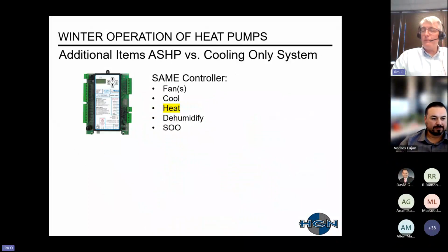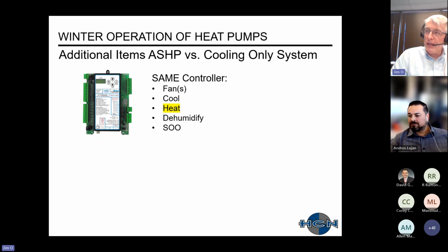And then just the other thing associated with rooftop units, the benefit of them is obviously pre-packaged, pre-canned, pre-engineered controls. Essentially, you're taking the same controller as for a conventional unit. You have your fan, cooling, dehumidification, and your sequence of operations are all essentially the same. I just highlighted that the heat gets a little bit more complicated when you start adding the air source heat pump with your supplemental heat, and then we'll talk about defrost, et cetera.